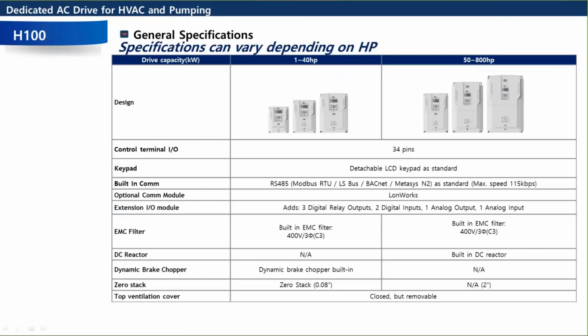Most of the time, 99% of the time, can't say never, you shouldn't need dynamic braking because on fans and pumps, usually it's not critical to stop them in a short amount of time. And you should just be able to extend out your deceleration time to counter an overvoltage trip.